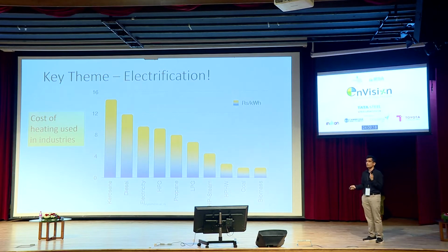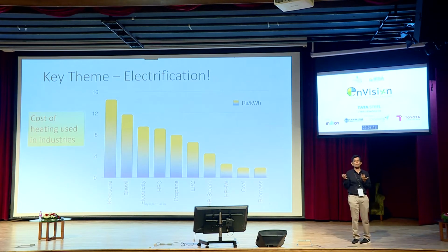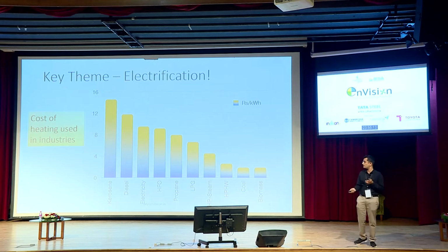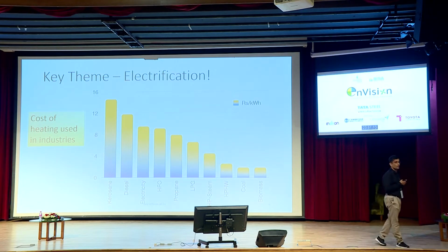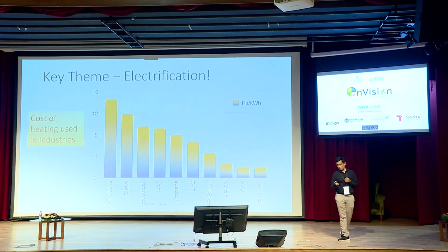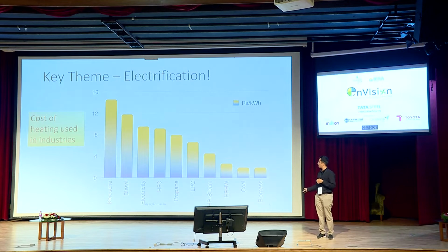That's where we're working hard to deploy what we call heat pump-based systems. There are two technologies I'll briefly talk about: one is the heat pump hot water system, primarily for applications that don't need heat above 90 degrees C, and the heat pump steam system, which we've uniquely developed in our lab and are trying to commercialize now. There, the focus is on low pressure steam applications.